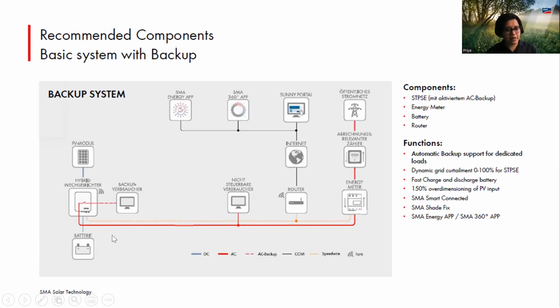So the PV and batteries are also going to supply to this load, but only when there is grid reference available. If grid reference is not available, these will not be supplied, but you will be able to supply entirely for this load, even though there is no grid available.